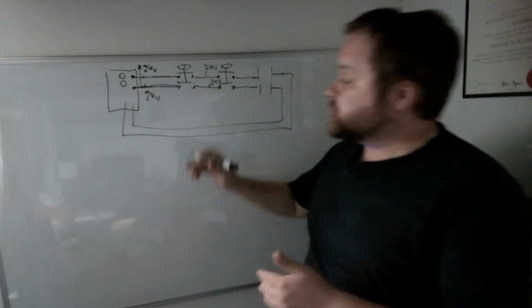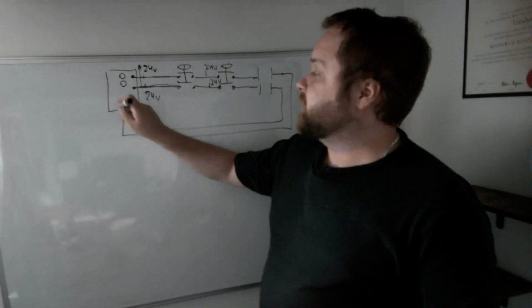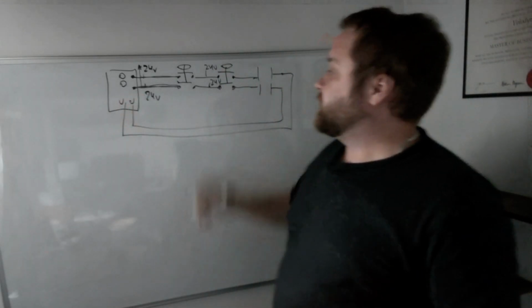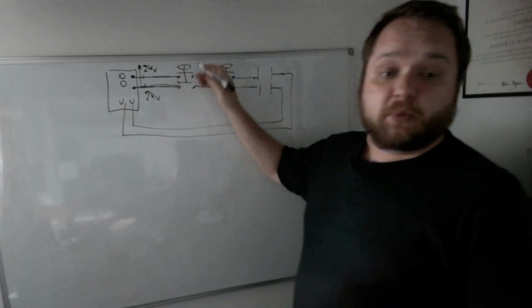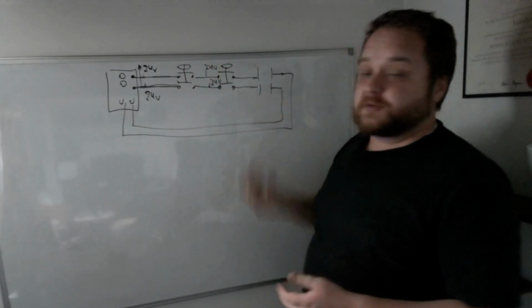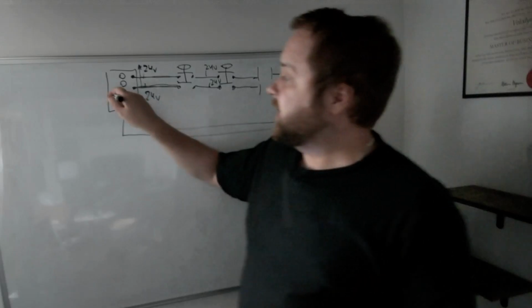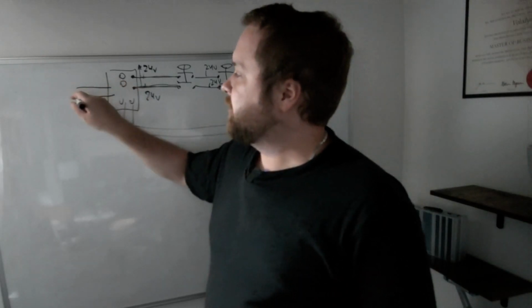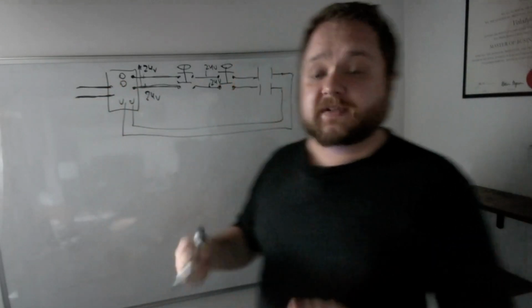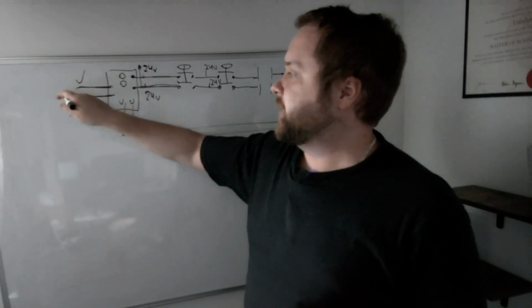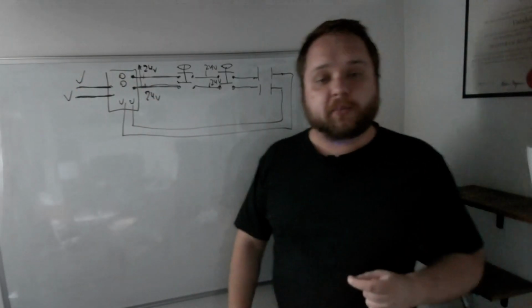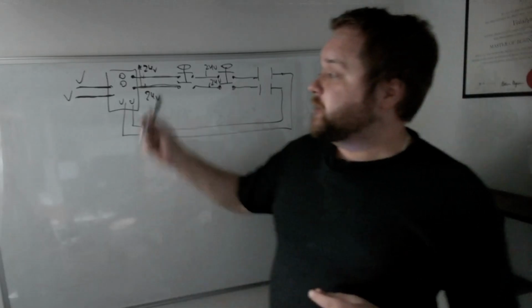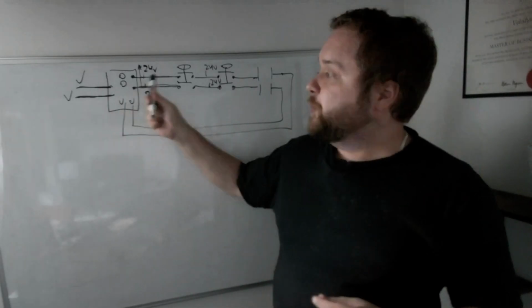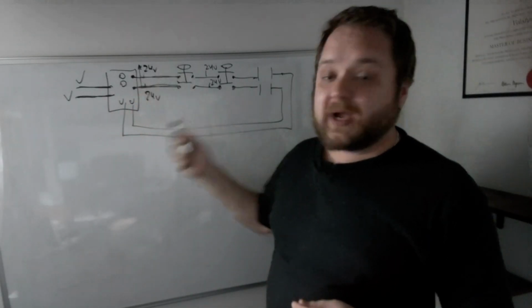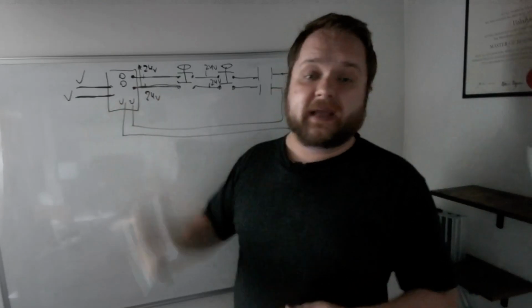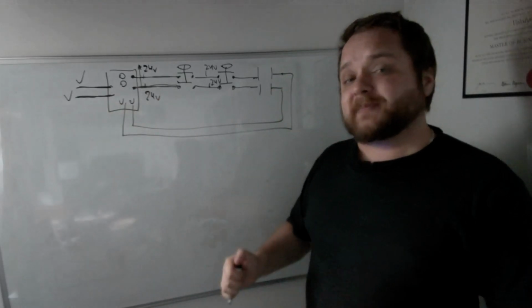And so once the channels are okay, right? If everything is correct and everything meets the safety requirement, again, the push buttons are not pressed, the light curtain is not obstructed, then you once again have 2 channels confirming that the safety is okay on both channels. And so here, it's very important to understand that as soon as you introduce dual channel safety, you need to basically have both channels correct in order for the relay to allow the downstream equipment to run.